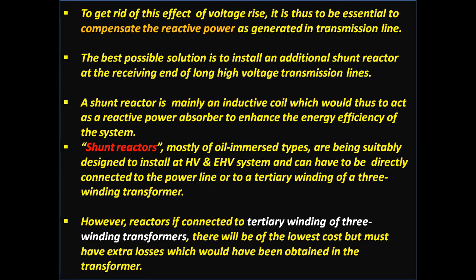The best possible solution is to install an additional shunt reactor at the receiving end of long high voltage transmission lines. A shunt reactor is mainly an inductive coil, which acts as a reactive power absorber to enhance the energy efficiency of the system. Shunt reactors, mostly of oil immersed type, are designed to be installed in high voltage and extra high voltage systems and can be directly connected to the power line or to a tertiary winding of a 3-winding transformer.